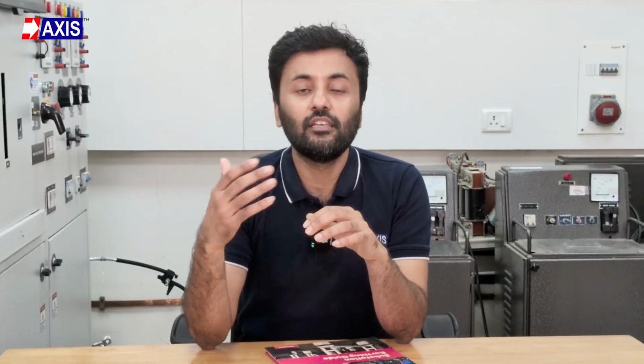If the bottom layer has lower resistivity or a water table is present, increase the length of the electrodes. This pushes them deeper into the more conductive zone. If the top layer soil resistivity is lower than the bottom layer, increase the density of horizontal grid conductors. This creates a denser mesh that spreads current more effectively through the conductive upper soil.